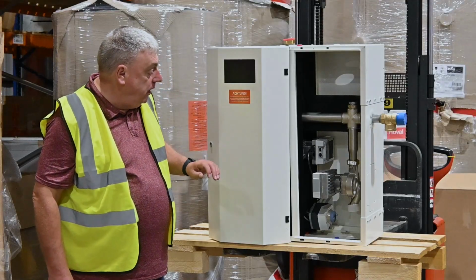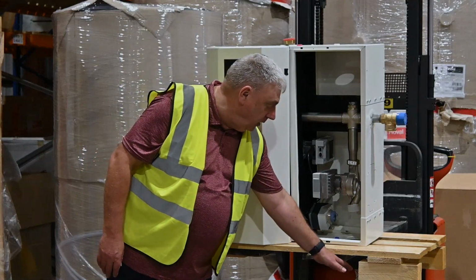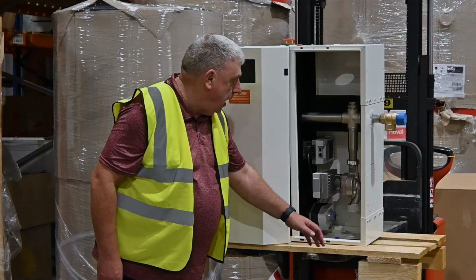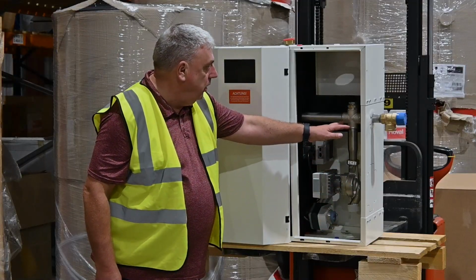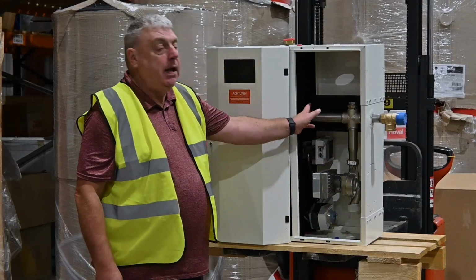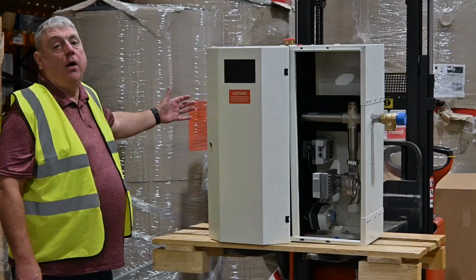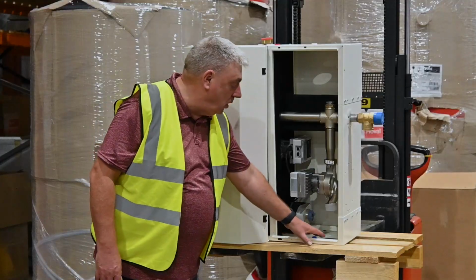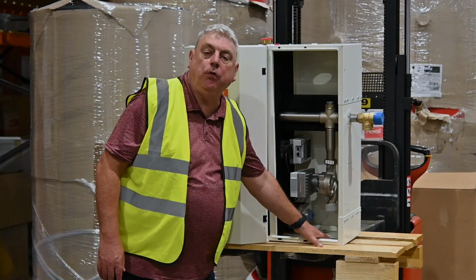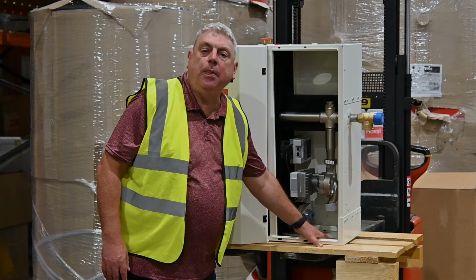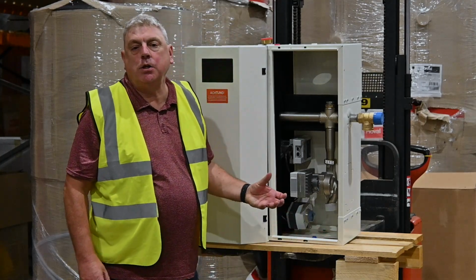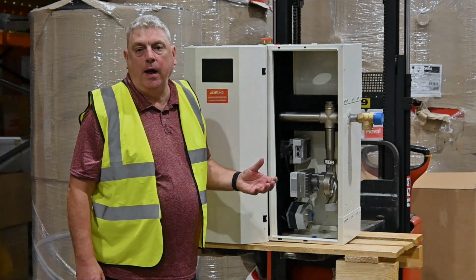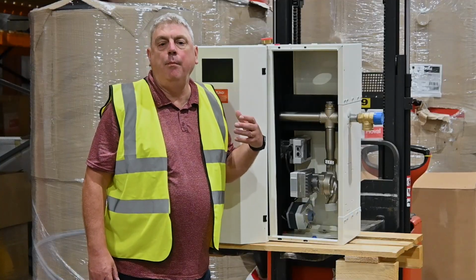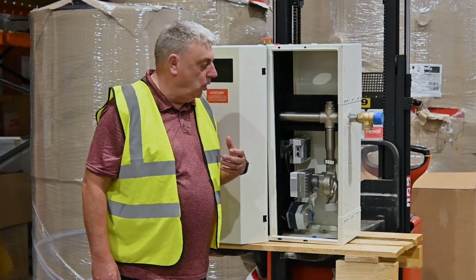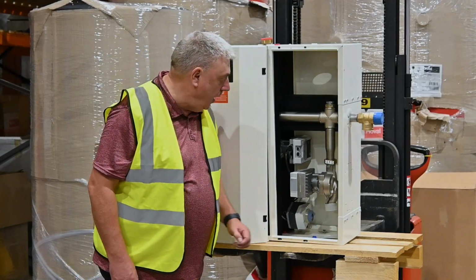And so what you have to imagine, with a little bit of imagination, is that we have the cold water coming in at the bottom here and going into this, via this pump, into the heat exchanger, which is round on this side of the unit. The mains cold water comes in at the bottom, and when we get them to site, we'll mount a little commissioning or balancing valve on there to control a measured flow rate on the cold water side through the unit.